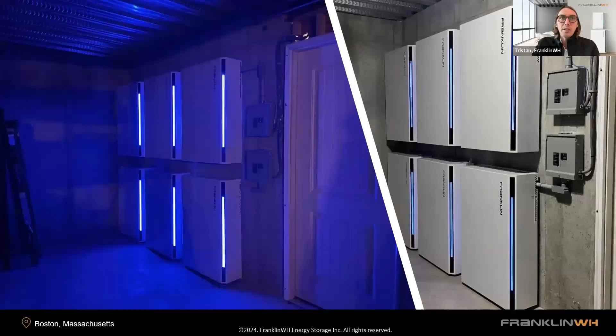All right, there's a question on fire safety codes. Are AHJs scrutinizing for enclosures to meet fire safety codes? Yeah, I mean, AHJs can be very particular. I don't know if the enclosure itself, but they do follow the UL 9540A listing very, very closely. So that 4-inch spacing needs to be adhered to. Most AHJs are asking for 6 inches, which is our guidance, even though 4 inches is okay. And then in some regions, we're seeing 36 inches spacing, which can tend to be a challenge, where having a larger capacity battery like ours is a good idea. And somebody's sharing that we are seeing some demand 2-hour rating closets. Yeah, not super familiar with that requirement. It could be in specific markets.